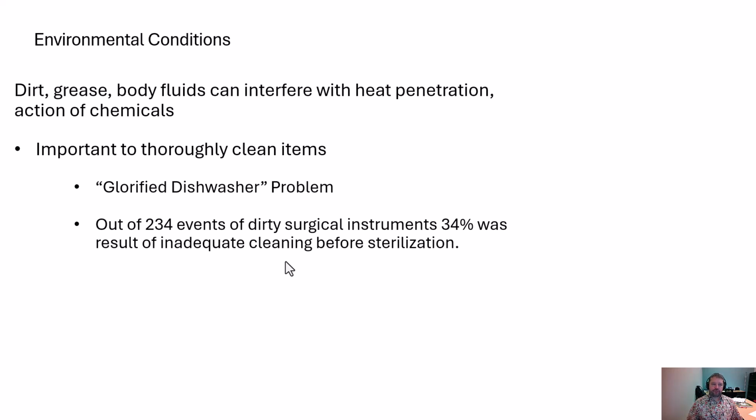So things like dirt, grease, bodily fluids were not removed, or not removed in a systematic way, and so therefore it didn't matter that you stuck it in an autoclave at 121 degrees for 15 minutes or 20 minutes or whatever. It didn't work. It didn't clean it.